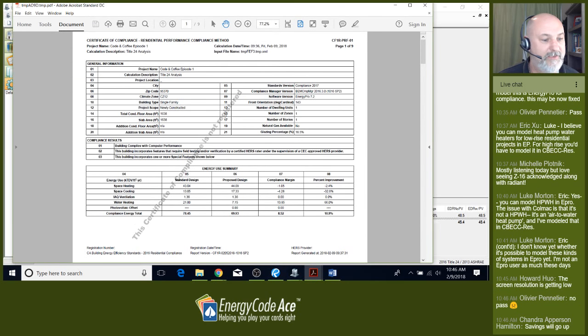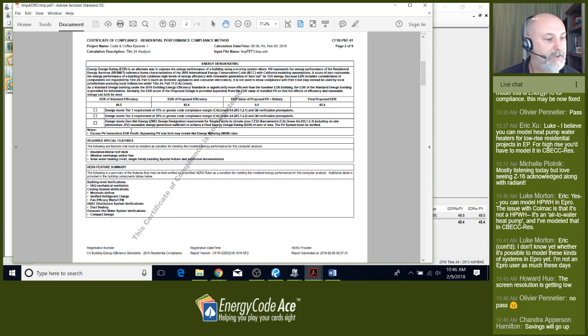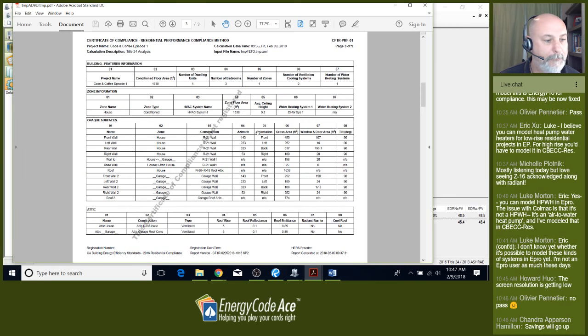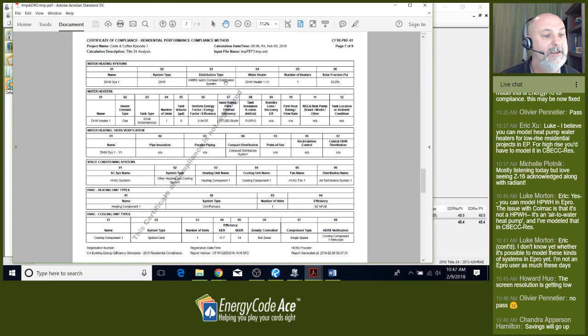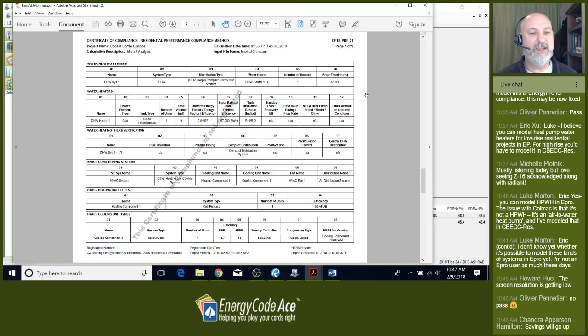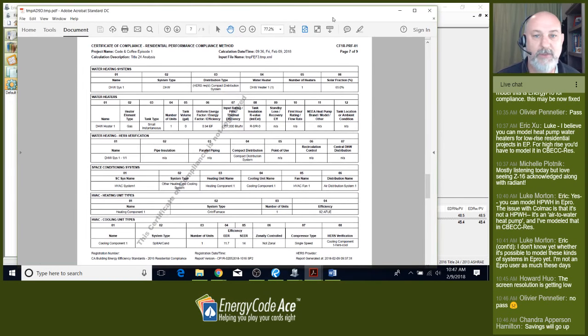Looking at the compliance documentation: on page two of the CF1R, under special features, we see solar water heating credit — single family building special features. On page seven of nine, water heating section: we included the compact distribution credit along with a 65% solar savings fraction. Compliance documentation is accurate — it modeled what we expected.